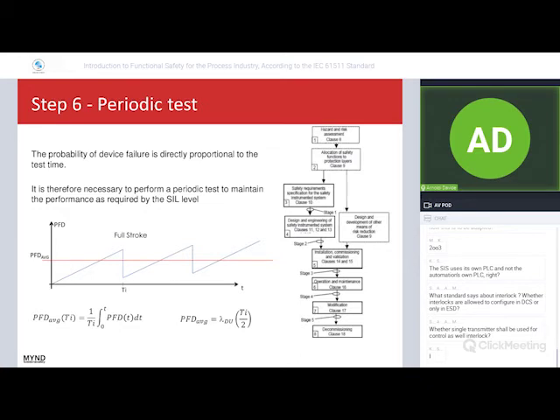Then I'm going to the end of this webinar. During the operation of the safety instrument system, somebody has to check the performance of the safety instrument function after, for example, 1 year, 2 years, 5 years. Because you have to think that the safety instrument function normally remains in one position for a lot of time. You have to be sure that in case of intervention of a SIF, this SIF activates correctly and then drives the process to a safe state.